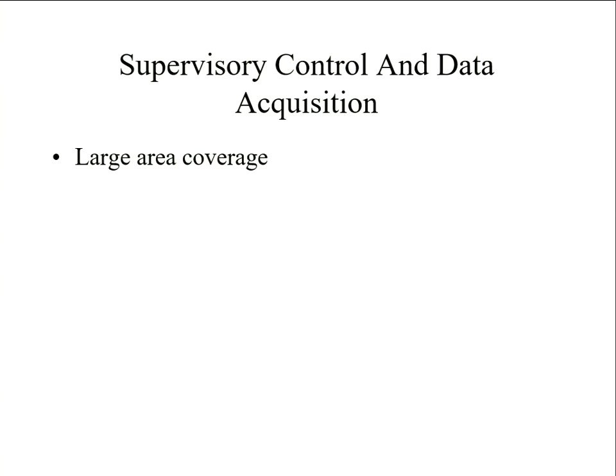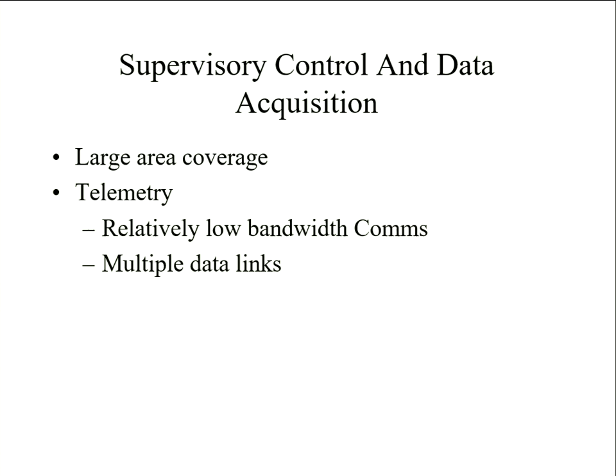So you'll have some form of central monitoring station, so lots of terminals, and actually usually lots of redundancy in here, and possibly even a second location. So if you have a fire and have to evacuate, or they're changing the carpets that weekend, now you've got somewhere to go. You can't not monitor a communications network.